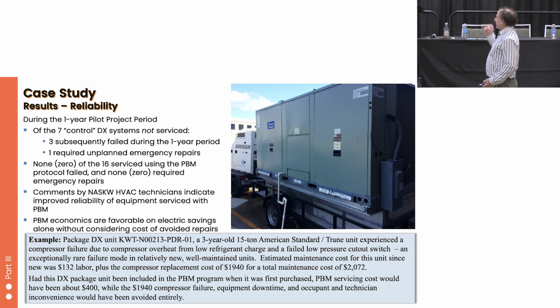The example here is this 15-ton American Standard unit. It had a compressor failure because of low refrigerant charge, which normally the low pressure cutout switch would prevent, but it also had a bad low pressure cutout switch. So the compressor ran with low refrigerant, overheated, and burned out. The cost to replace the compressor and everything was a couple thousand dollars.